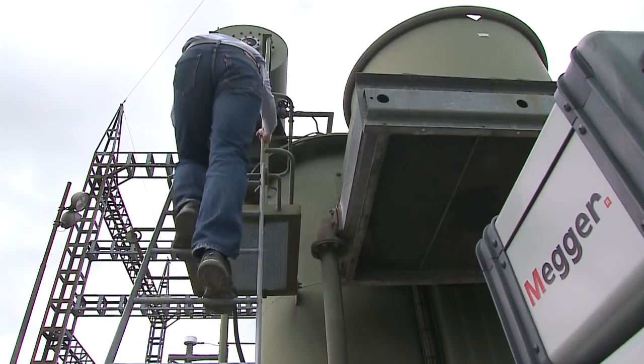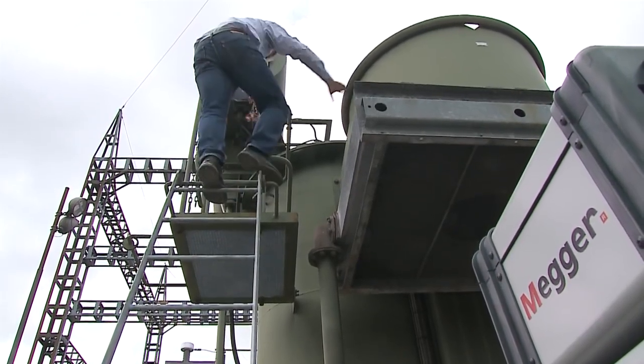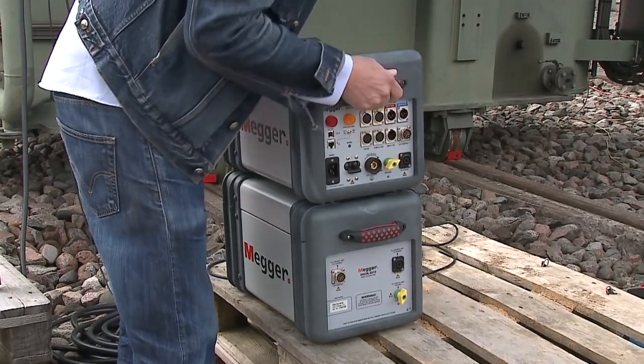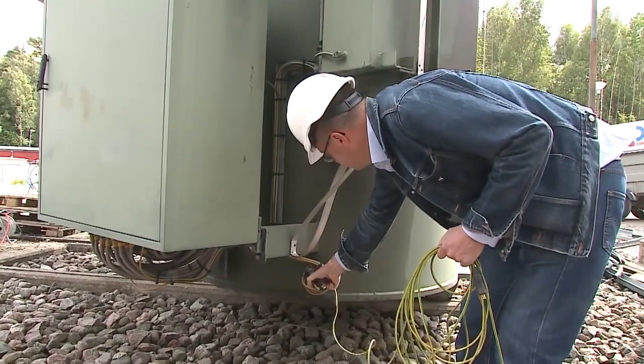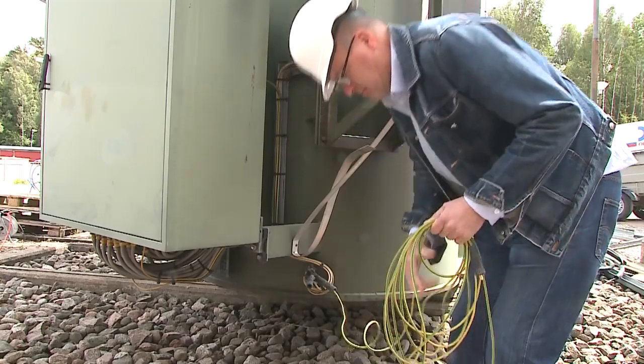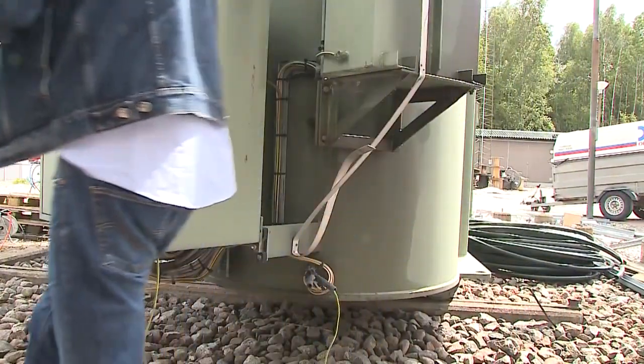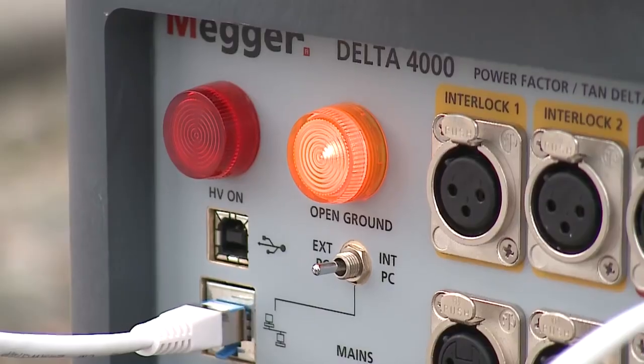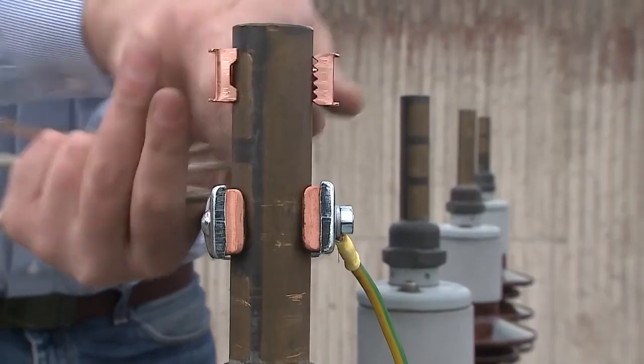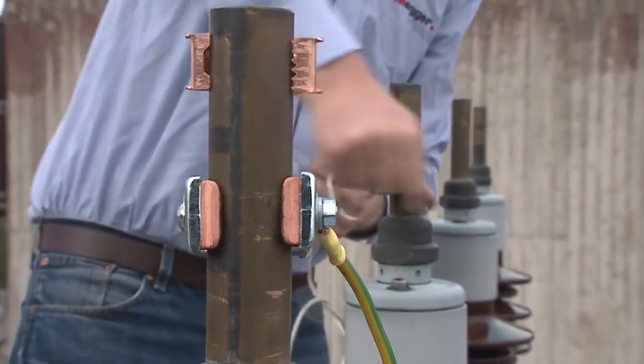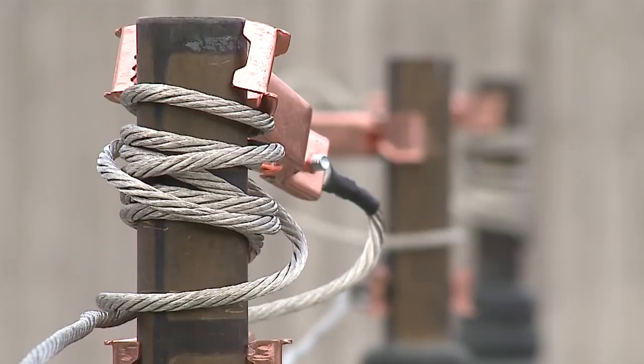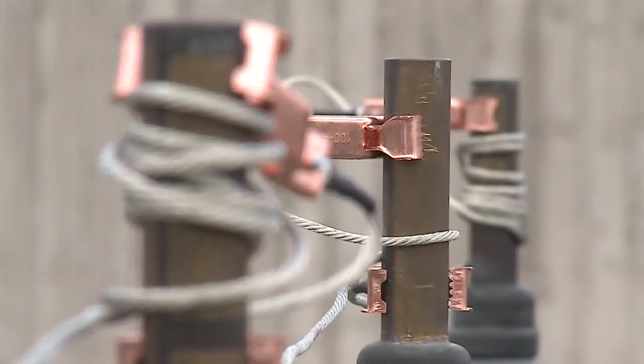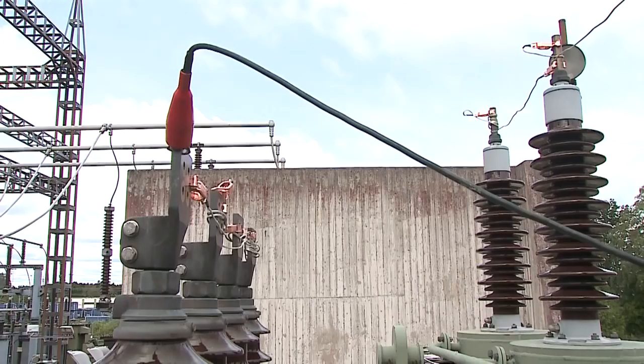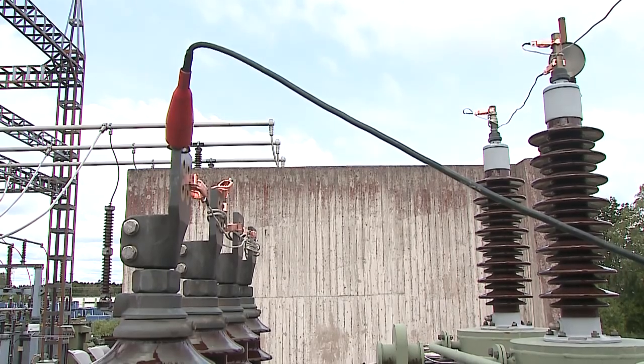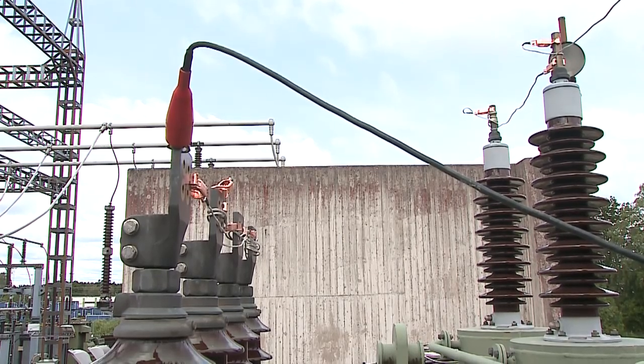Preparations and connections. Remove all connections to the transformer bushings, including lightning arresters and bus bar. Isolate neutral winding from ground connections. We prepare the Delta 4000 by connections to transformer ground. Short all phases for each winding together, ensuring shorting leads do not droop. Connect HV and low voltage red lead to windings. Transformer is now ready for testing.